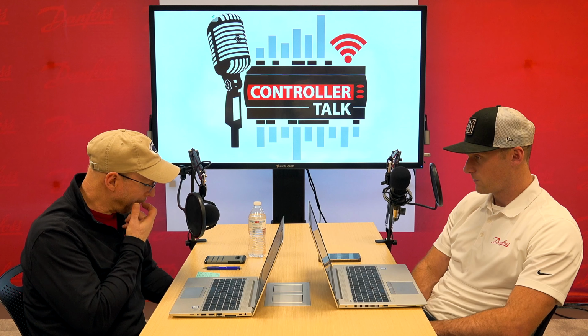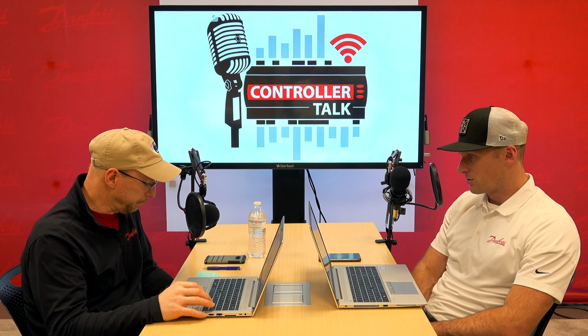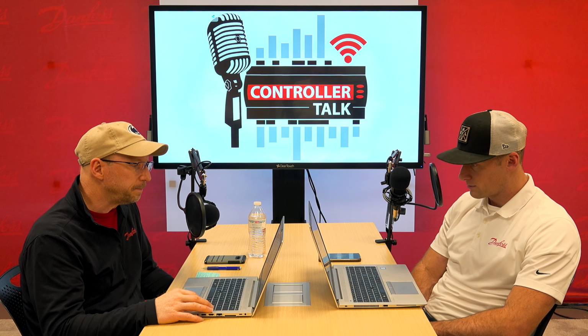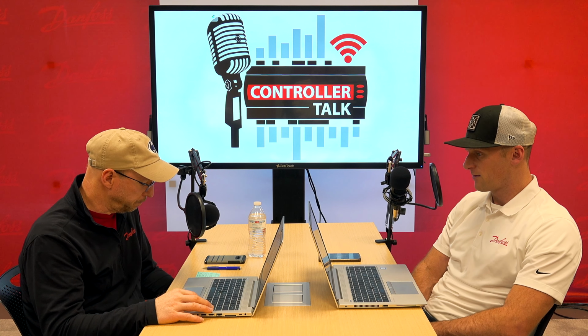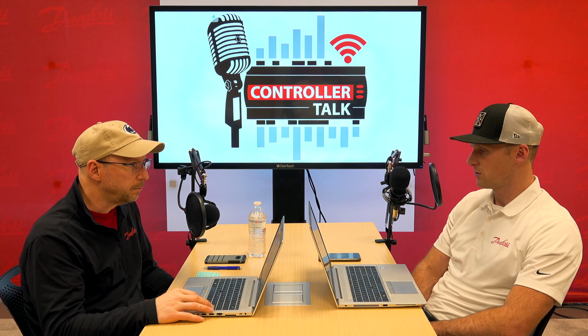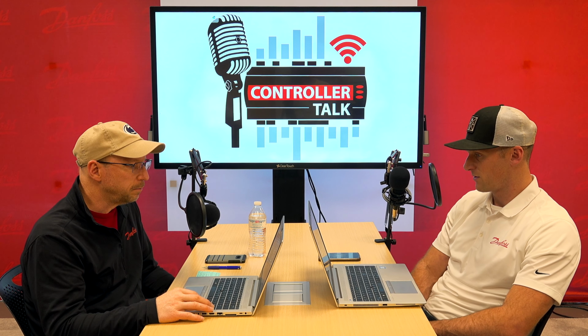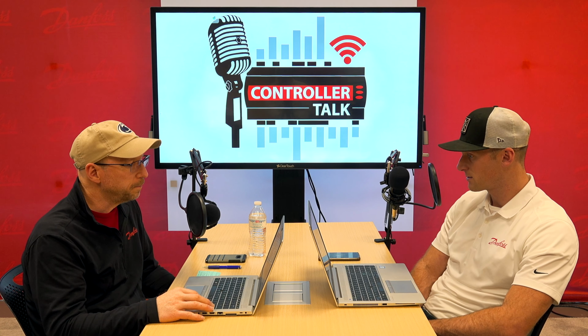Just a final few points here. Back in the system manager side, we have our schedule section. You see all different uses for that—defrost schedules is probably the most common one, case lighting is a close second. But you want to review that section. Your defrost schedules that you have set up have to be assigned to specific case controllers, so make sure that's configured right, or else your cases might not defrost.